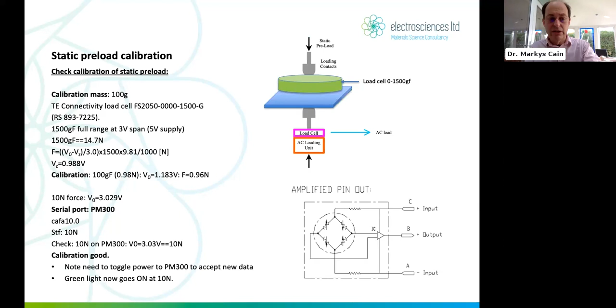We've calibrated the static preload. Good. We have a D33 response calibrated for quartz and lithium niobate. These are fairly standard, robust, solid materials. Sure, we can go to higher piezo coefficient materials. We might even go to single crystal materials, which are possible. Well, the relaxors, they're not actually that stable, are they? Anyway, we can use that quartz and lithium niobate to recalibrate the standard reference samples that come with the Berlincourt tool, and we do this regularly. We have to do this on a regular basis. I would suggest almost each time we use the equipment, if you turn it off, you'd have to redo this.